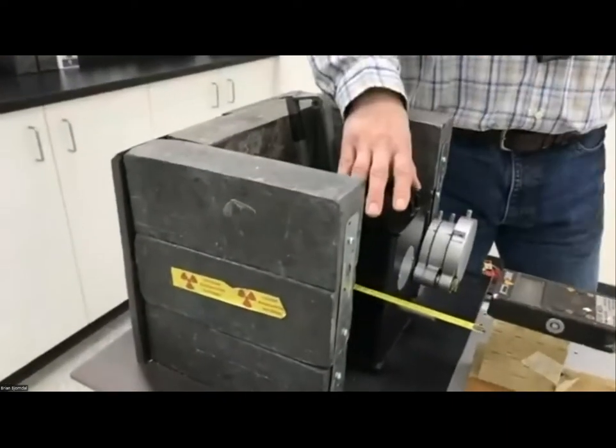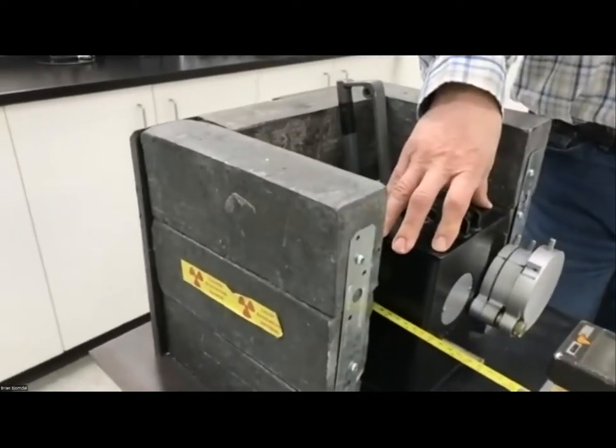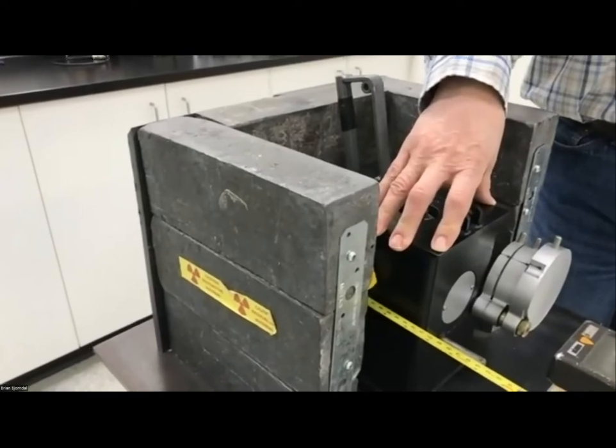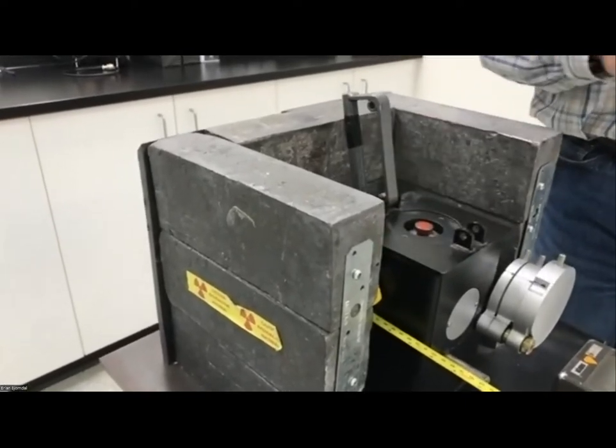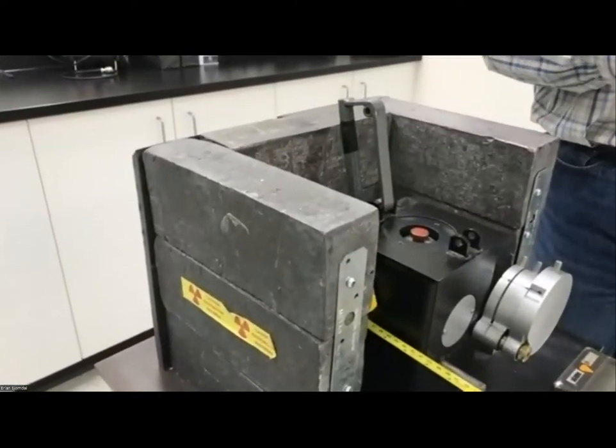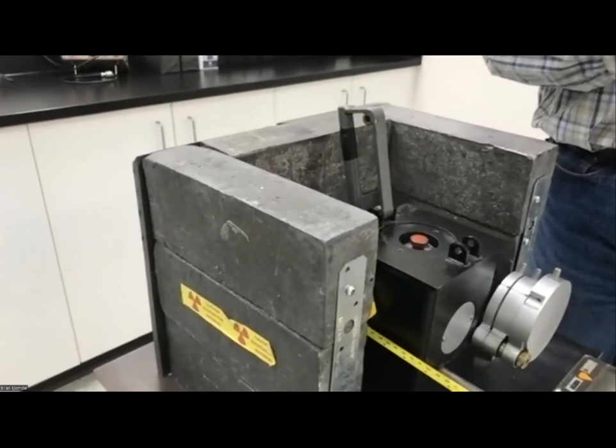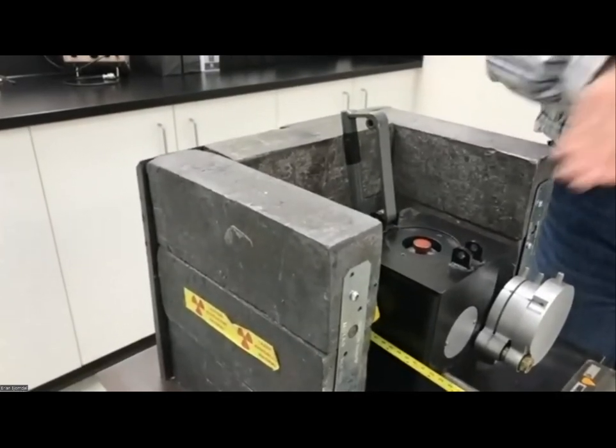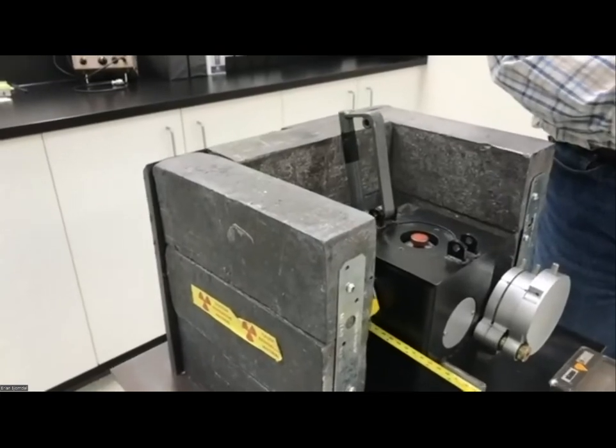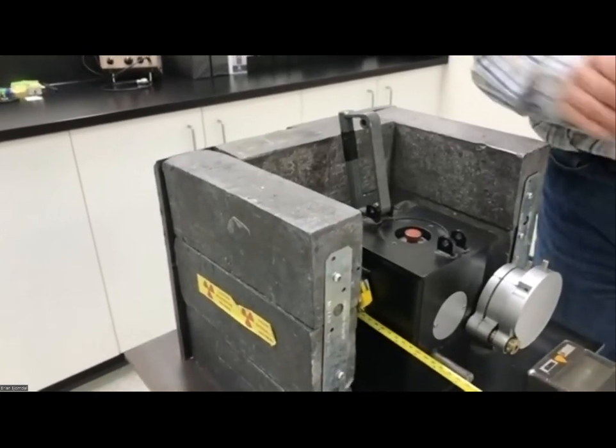So this is a NIST traceable source, and we have to do a calculation to do decay correction and to calculate what the expected dose rate is, based on what is desired and the distance between the source and the detector being tested. So I'm just going to turn.